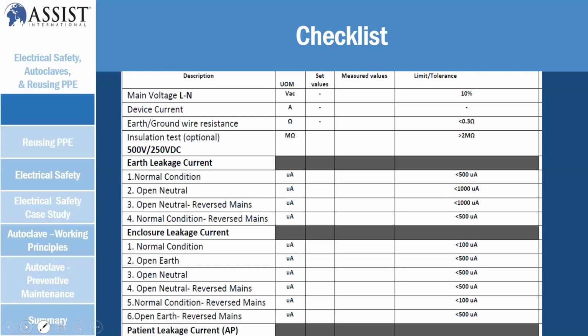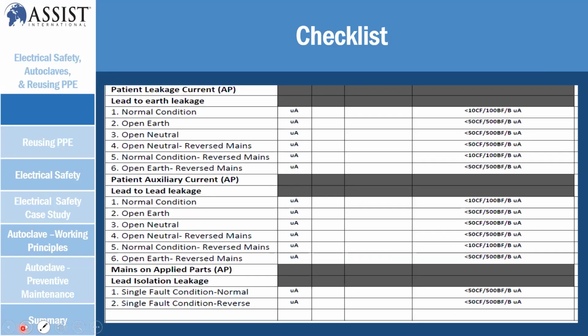On patient leakage current, you have lead to earth leakage, and patient auxiliary current, which is lead to lead leakage, and mains on applied parts, lead isolation leakage. So particularly when you talk about AP, applied parts, you are talking about things like ECG, all that you're going to measure.